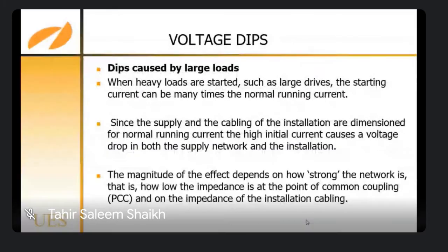Dips caused by large loads. When heavy loads are started, such as large drives, the starting current can be many times the normal running current. Since the inrush current will be very high, the voltage will drop. Since the supply and the cabling of the installation are dimensioned for normal running current, the high initial current causes a voltage drop in both the supply network and the installation.